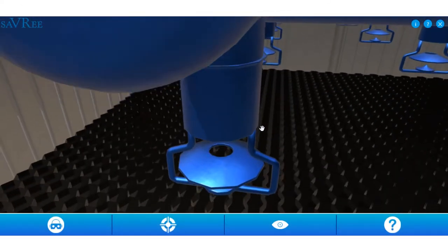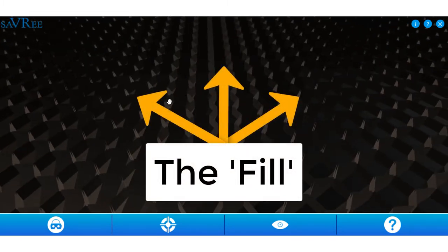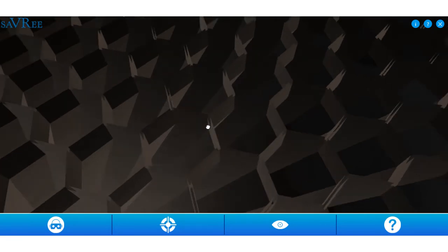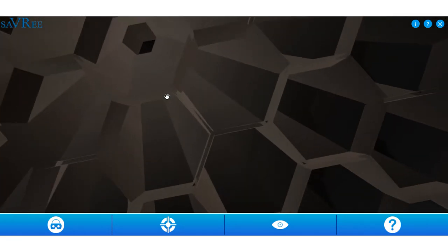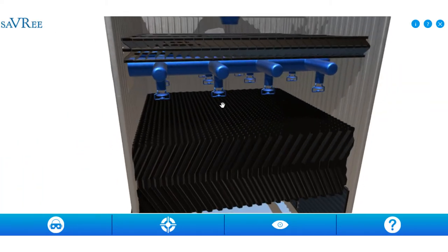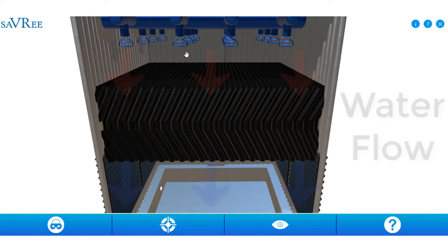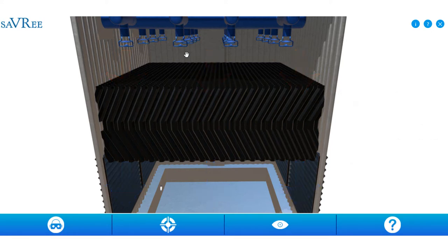Looking down, we can see a dark item called the fill. The water is going to land on the fill and trickle down into the holes. The water sprays out of the nozzles into a spray pattern — loads of raindrops falling onto the fill, which is a heat exchanger. Those raindrops form a film of water, meaning a thin layer of water all over the heat exchanger, so the cross-sectional area within that heat exchanger is very large.